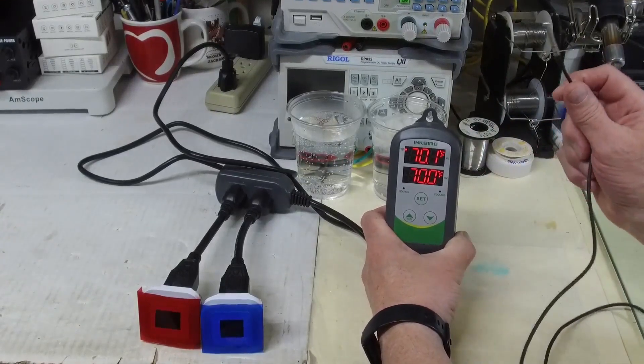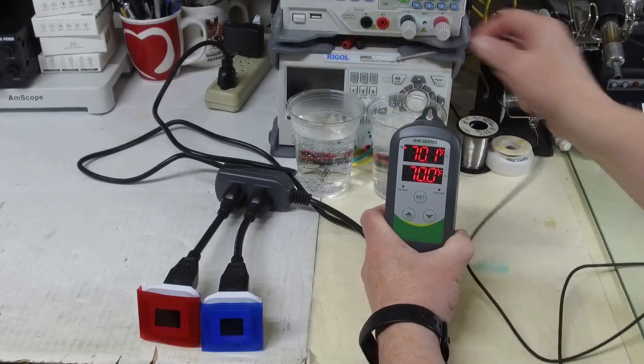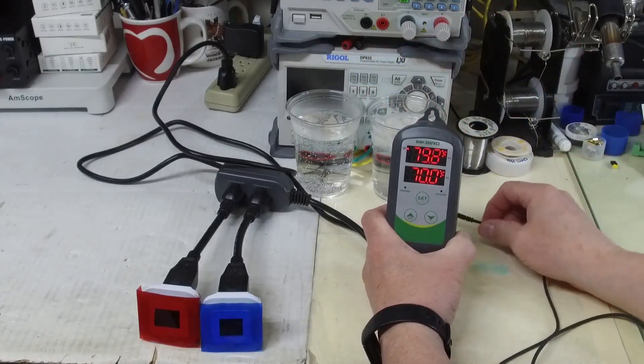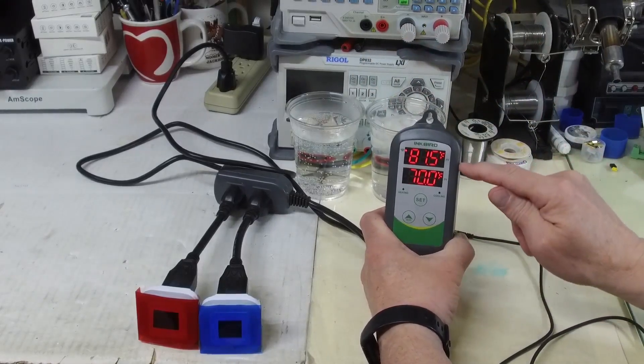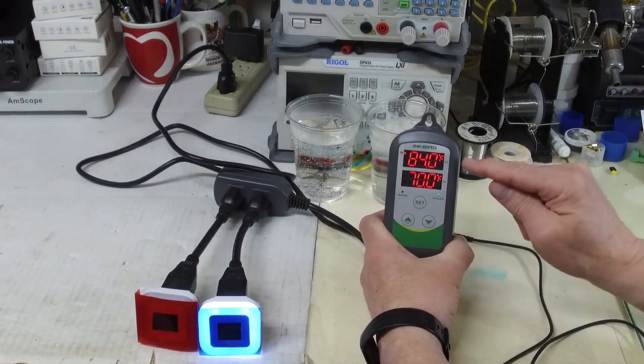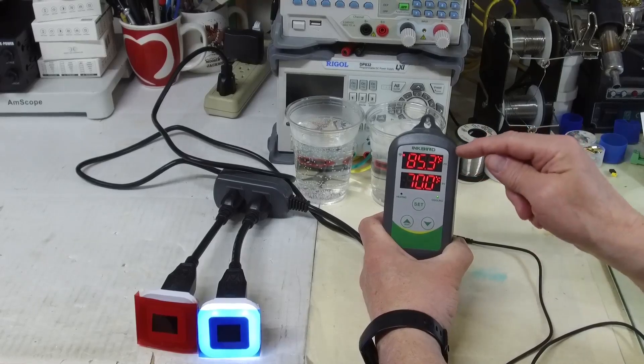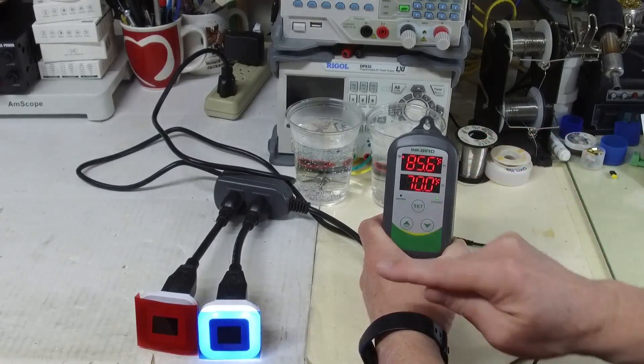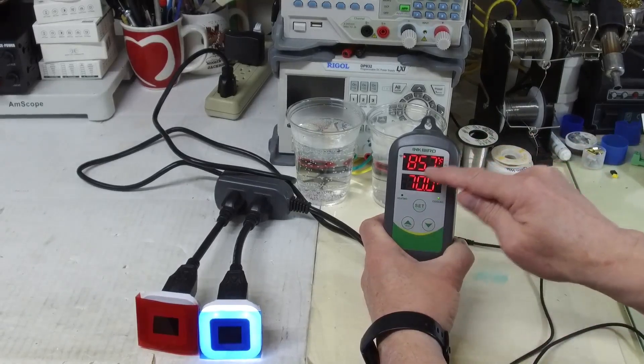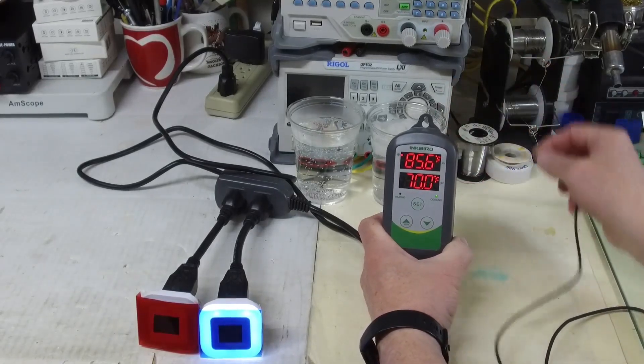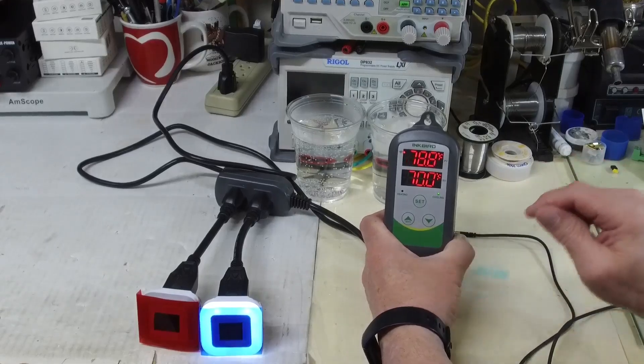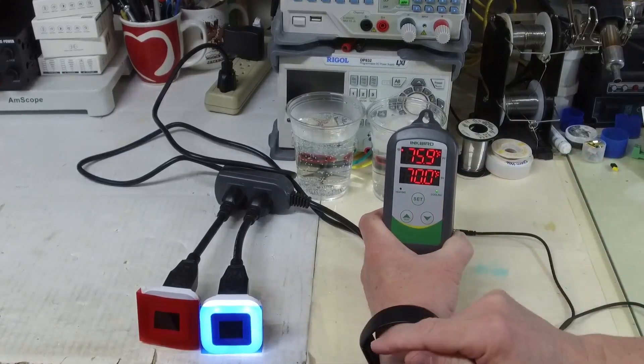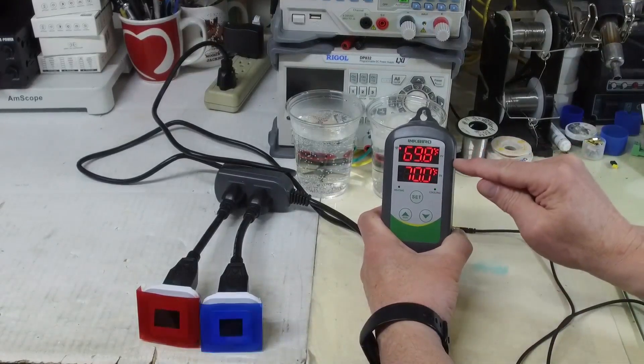So I'm going to put this probe in some hot water. It's going to go up to 80 degrees. The cooling is turned on and the cooling will not turn off when it hits 80 degrees. So I just gave it a quick—see it's still on—and it's not going to turn off until it gets down to 70.